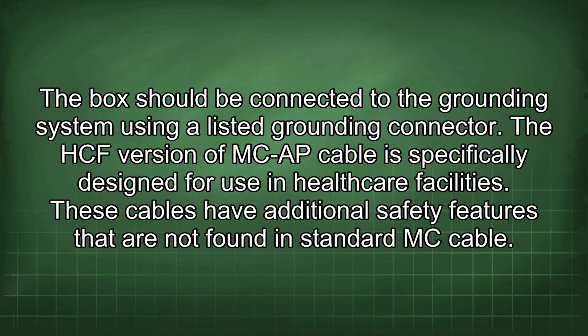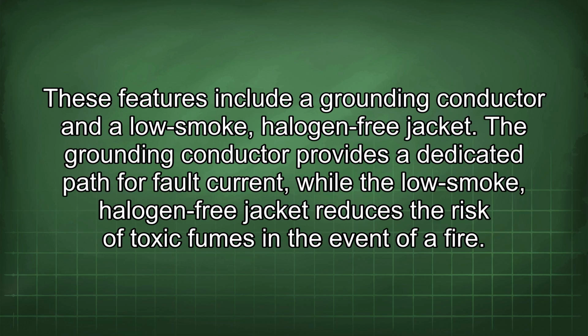The HCF version of MCAP cable is specifically designed for use in healthcare facilities. These cables have additional safety features that are not found in standard MC cable. These features include a grounding conductor and a low-smoke halogen-free jacket. The grounding conductor provides a dedicated path for fault current, while the low-smoke halogen-free jacket reduces the risk of toxic fumes in the event of a fire.